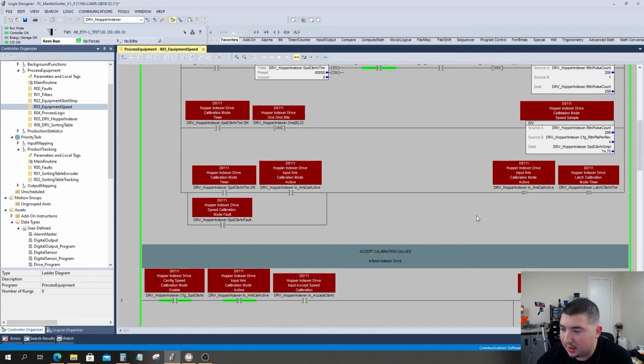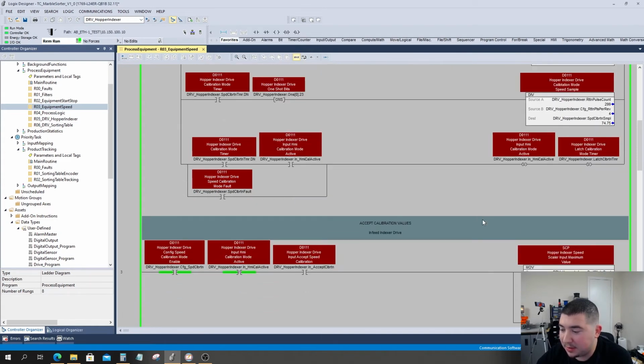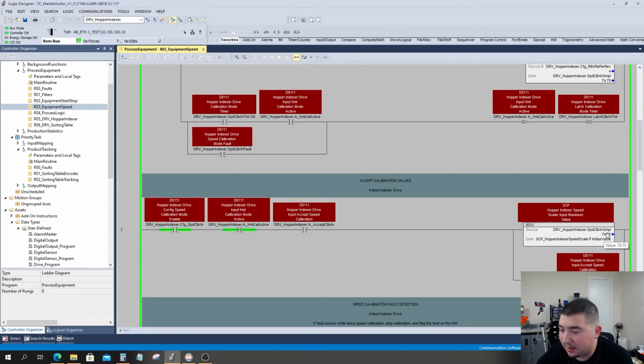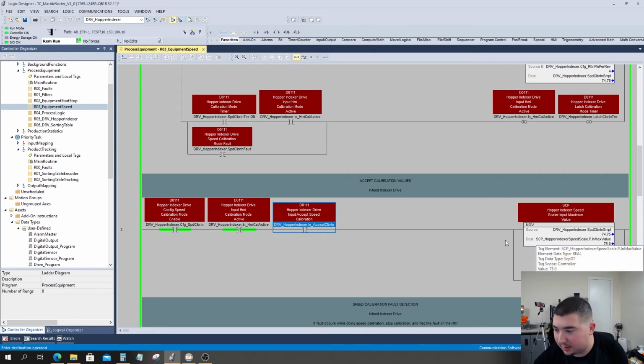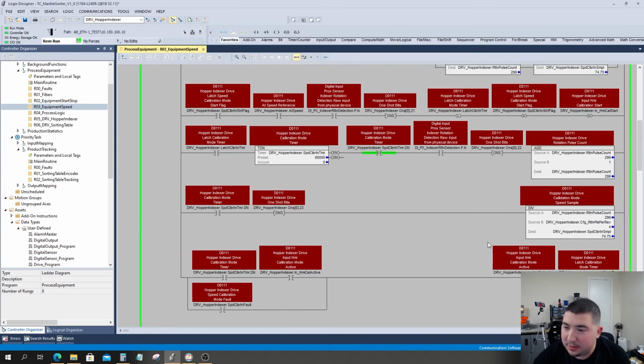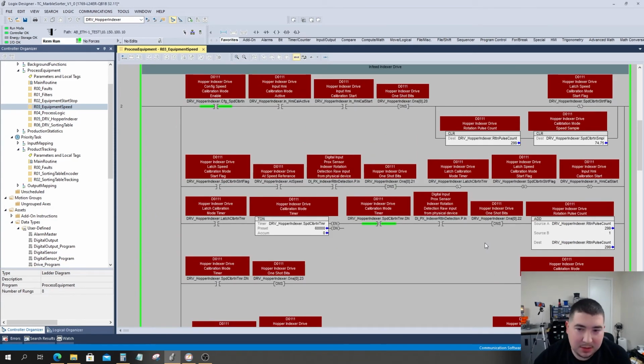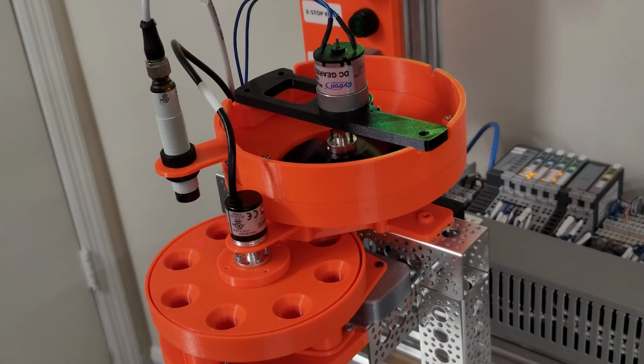That was our sampled speed, which is a little bit lower than what our actual max speed was. If you remember, our max speed for that motor was 75. So as you can see, we've got 75 as our original value, and our measured value is 74.75. If I hit accept, it'll move this value into our speed check maximum. So we'll do that. It's stored the value. As a sanity check, I always like to do the speed test again after doing a recalibration. So we'll again start the calibration mode, and we will start the motor.